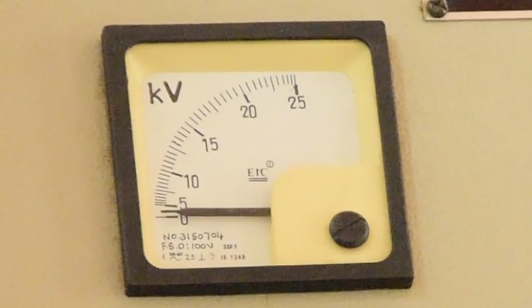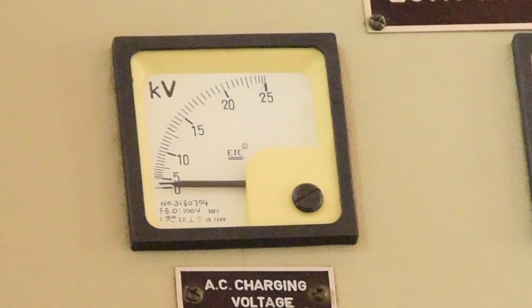Again I have released the switch, and again I am pressing it - you can see the dial. There is an arrangement here that memorizes the last reading by noting the position of the variable control dial of the dimmerstat. So wherever the failure occurred, the reading to be taken here is 8 kV, and the breakdown strength can be calculated based on the formula available in the description.